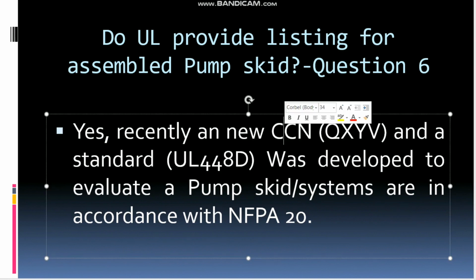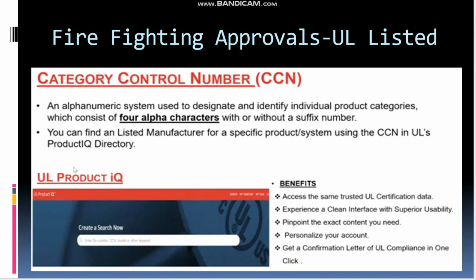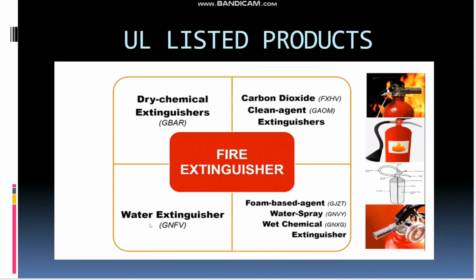Here we saw the word CCN. The CCN is nothing but a category control number. Normally in UL, if you want to see who the approved manufacturers for fire pumps are, you can check the CCN number. You can find a listed manufacturer for a specific product using the CCN number. A CCN is nothing but 4 alpha characters with or without a suffix number. Sometimes there will be a suffix number, sometimes not. For example, for this fire extinguisher, a dry chemical extinguisher, GBAR, there are only 4 alpha characters, and all these fire extinguishers come without any suffix number.